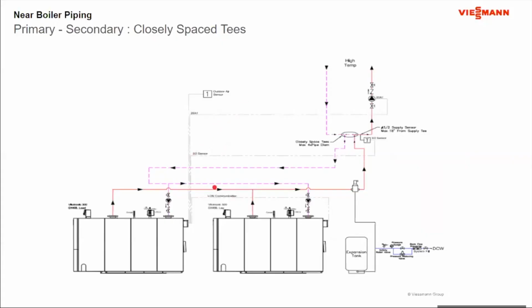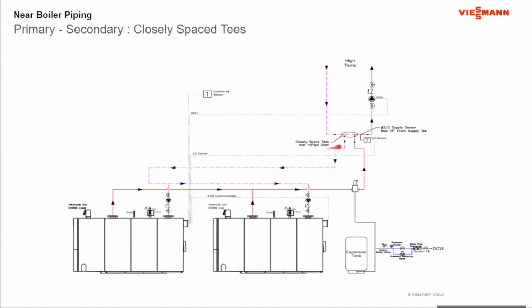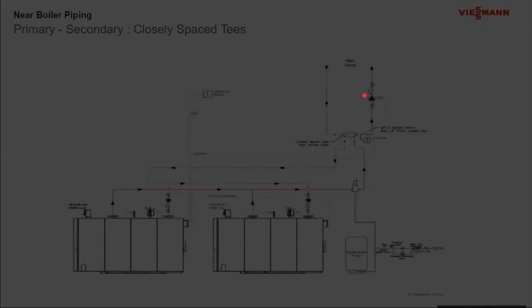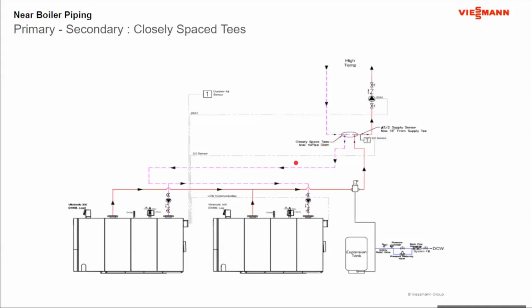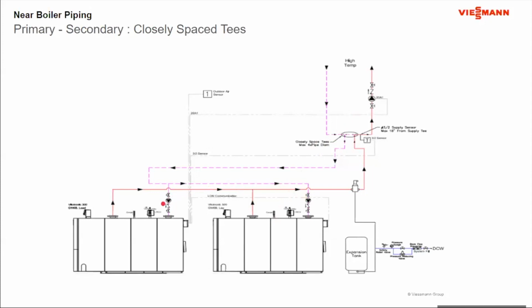Okay. Also, I can do primary secondary with floor standing boilers. So you have the same thing here. Here are my closely spaced tees. There again is my max 4 pipe diameters. And it gives me, again, the ability to bring the boilers outside of the system loop, put them in their own boiler loop, and allows me to design specifically for what I would like to see for a delta T across the boiler, regardless of what I'm going to see for a delta T across the system. Okay. The other thing it does, from a pipe pumping standpoint, is that the system pump doesn't have to be sized to flow water through the system and the boiler. This pump is sized for what's needed for the heating loop. These pumps are sized for what's required for each individual boiler. So there are advantages when I start to go with the primary secondary versus the variable primary.